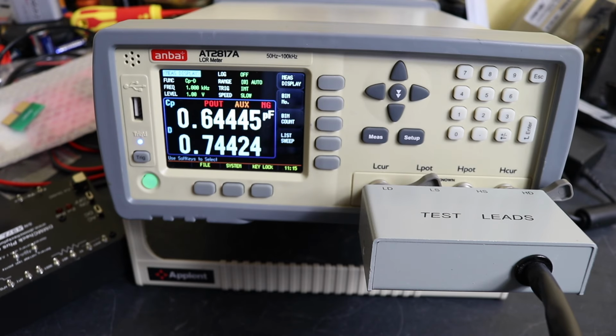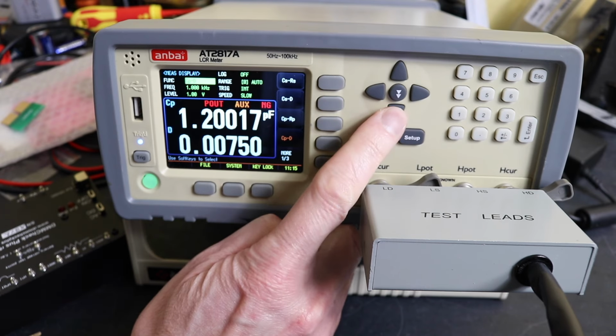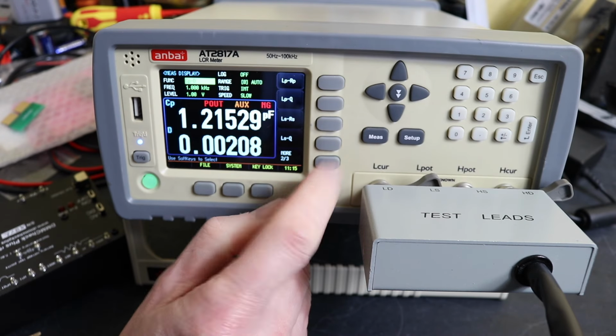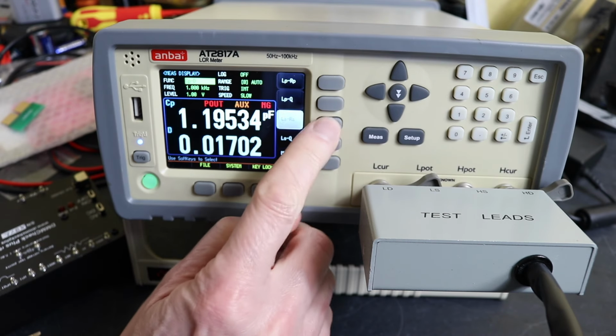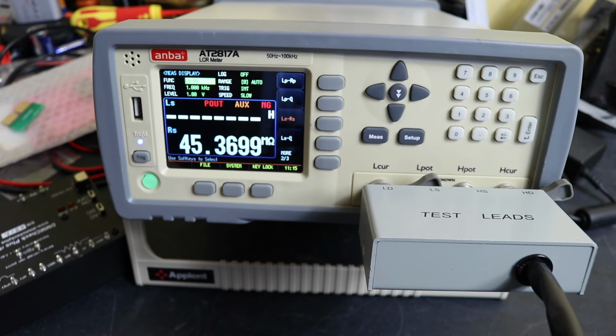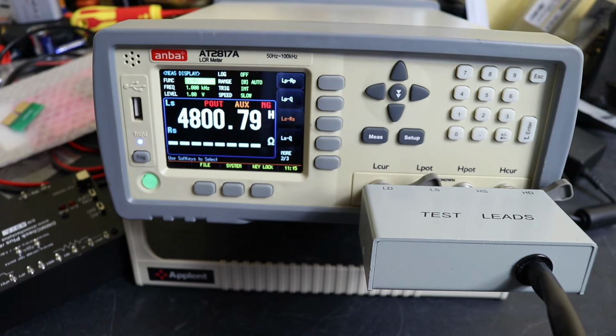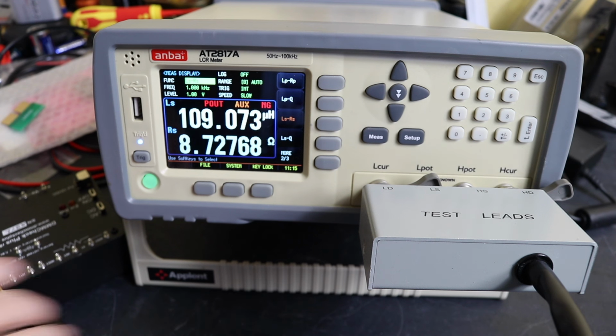We will measure our 100 microhenries. No, we won't, because we'll select that first. Let's go LSRS. We'll put him on to our 100 microhenries. And on this one we get 109.15, which is pretty close to what it's always been with this instrument. I regularly measure the DMMCheck Plus with this instrument, and the values are consistent across the time span that I've measured it with this instrument. Although 109 is a little bit high, it's certainly not 0.05% within the 107.2.